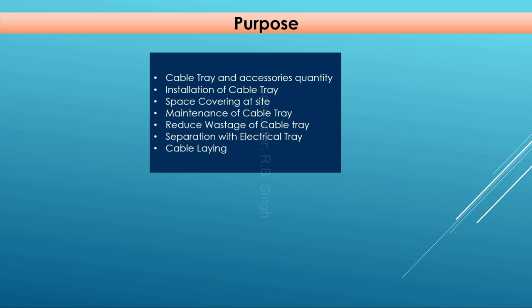Another purpose is space covering at site. There are different stages of cable tray layouts, and since the electrical engineer and pipe engineer also work on the plant, if we do not cover the space early, at the time of installation we may find no space or routing available for the cable tray. During detail engineering, if we make the cable tray layout, we can cover the route and space so that there will be no problems during installation at site.